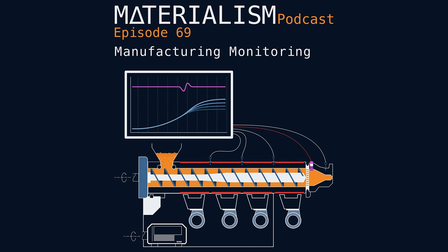And it's interesting, as you center this device, the dies actually are compressing and moving a little bit. And so you actually have to move the aim of that optical measurement so that it stays fixed on the tiny hole, right? Because if the die moves and all of a sudden you're not pointing at the hole, well, the outside of the die is going to be much colder than the inside. And so sometimes you'll see this huge jump in the temperature from your optical measurement. And it's pretty clear that what happened is that you stopped looking at the little tiny hole that you were supposed to be looking at.